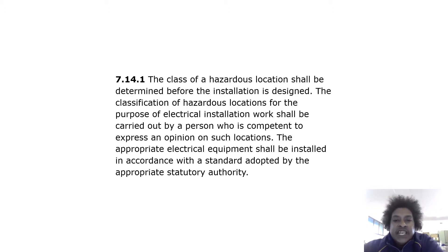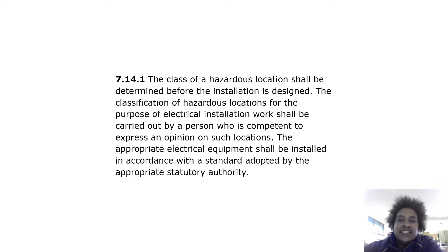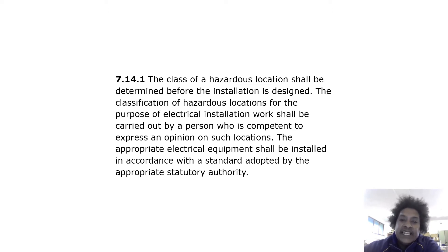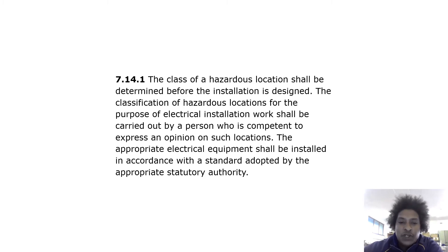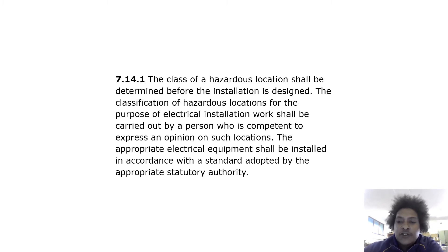The class of hazardous locations shall be determined before the installation is designed. The classification of hazardous locations for the purpose of electrical installation work shall be carried out by a person who is competent to express an opinion on such locations. The appropriate electrical equipment shall be installed in accordance with the standard adopted by the appropriate statutory authority.